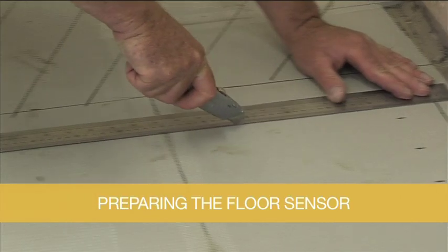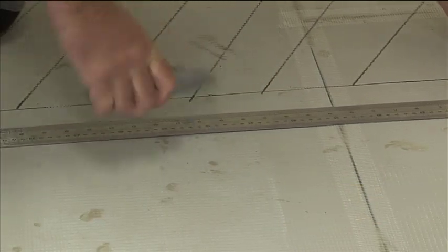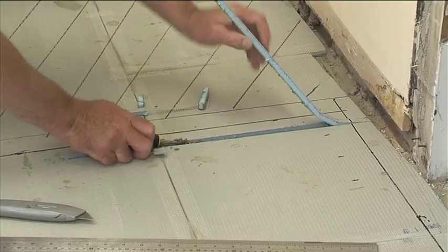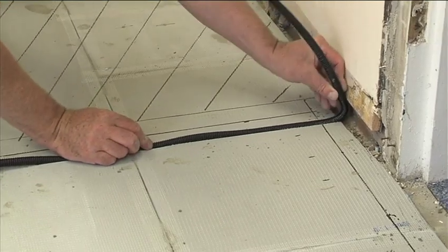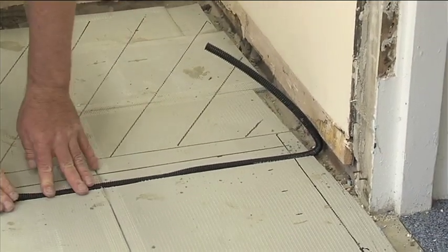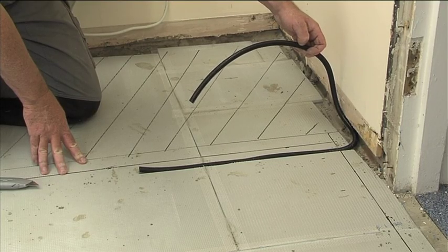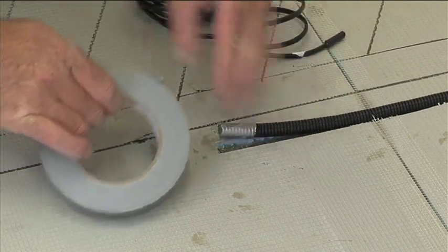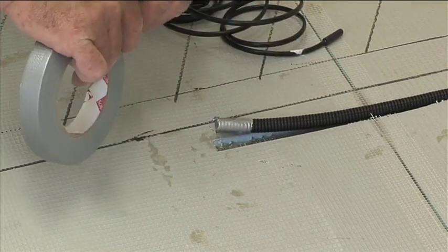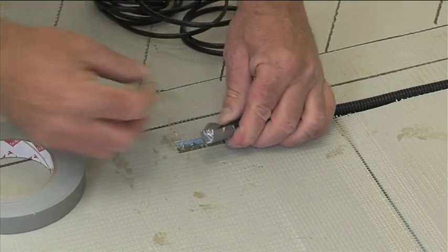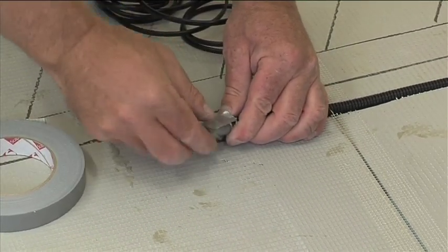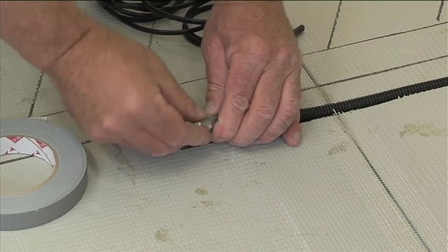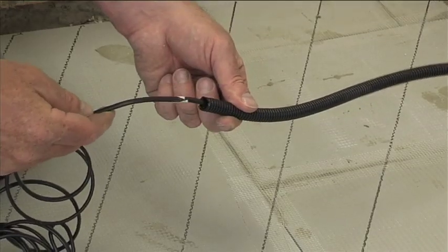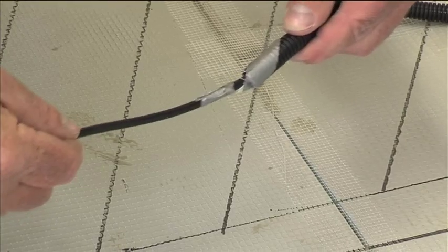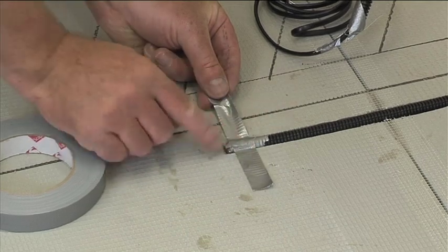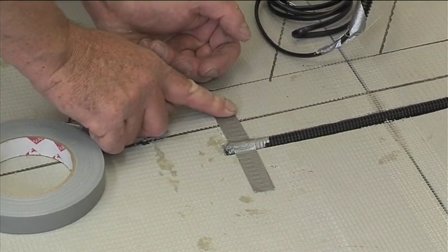Before commencing laying the cable, cut a groove in the floor to accommodate the floor sensor for the thermostat. The sensor should be installed in the 12mm diameter flexible conduit supplied with the kit. The sensor should be positioned between two cable loops approximately 500mm into the heated floor. Seal the end of the conduit with tape to prevent adhesive entering. Insert the sensor and tape to prevent it being accidentally removed. Insert the assembly in the groove and tape into position.